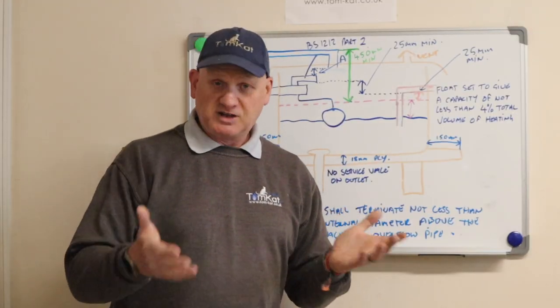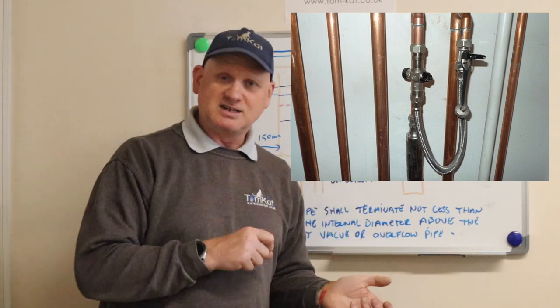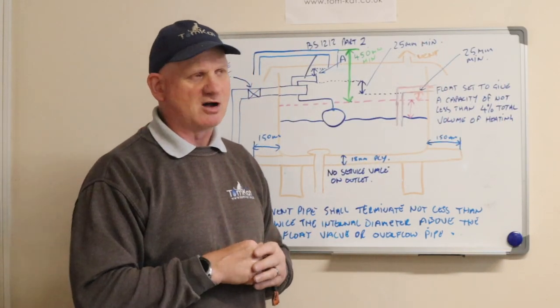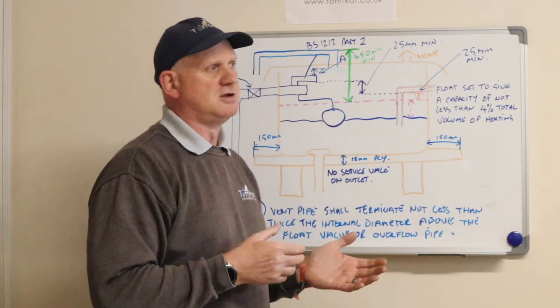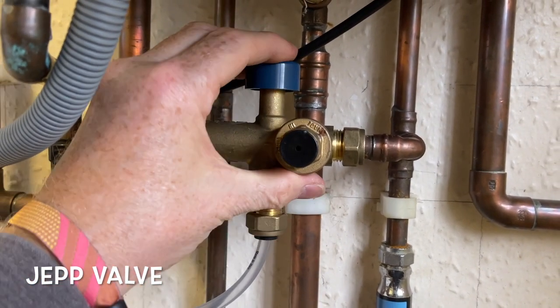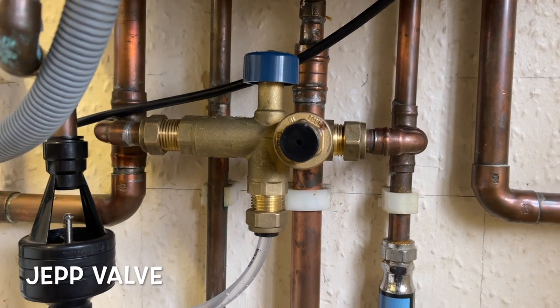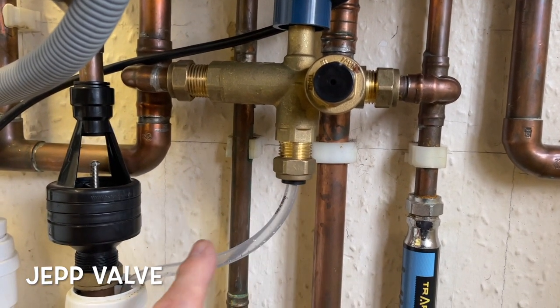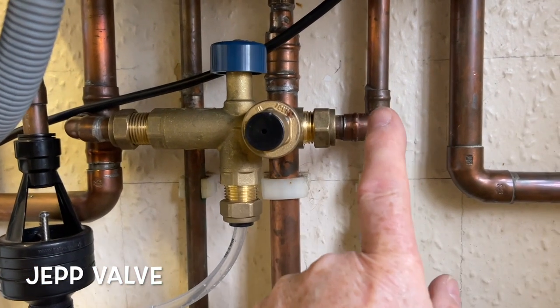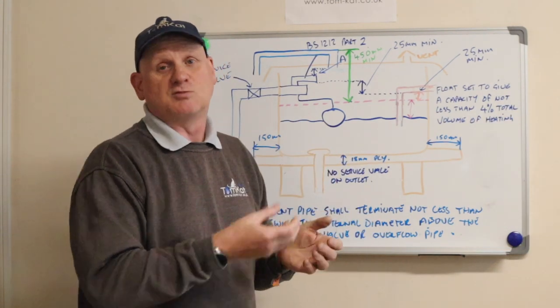Combi boilers use filling loops with double check valves, and they get away with it because the filling link is only connected when filling the system - that's why we need to remove the filling link afterwards, or fit an RPZ (reduced pressure zone) valve. You could also use a Jepp valve, which is an automatic fill valve. When you press the button it has a pressure reducing valve so you can never exceed pressure, and it also has an RPZ valve that can discharge water to drain if the pressure on one side is greater than the other.